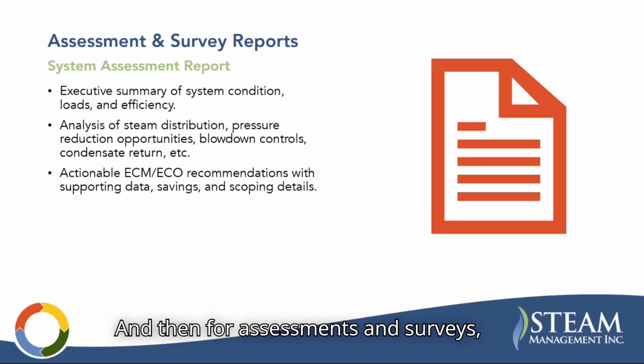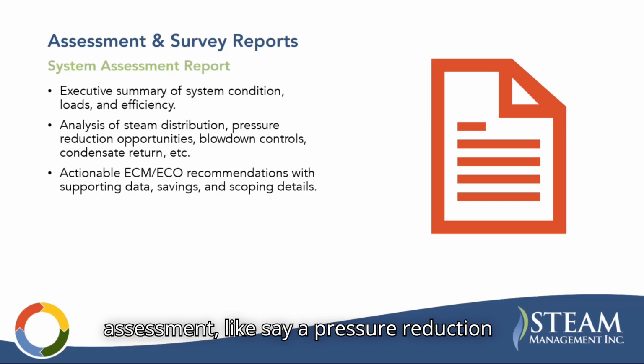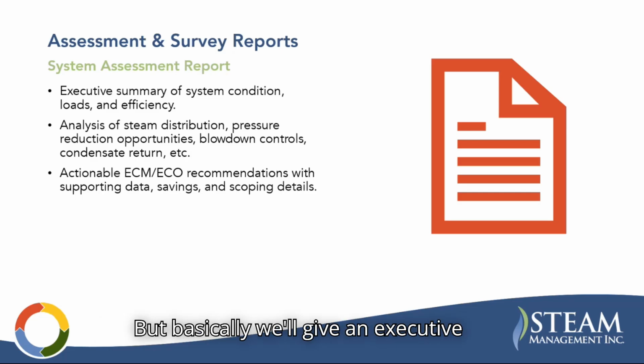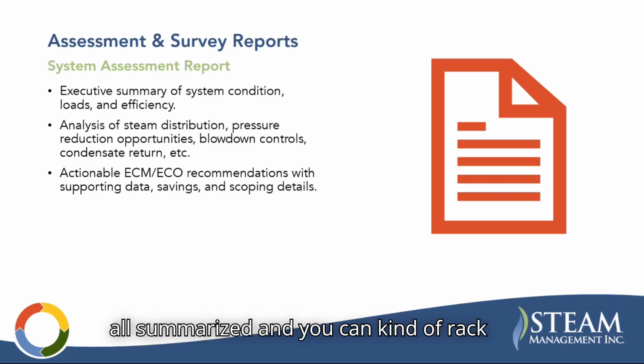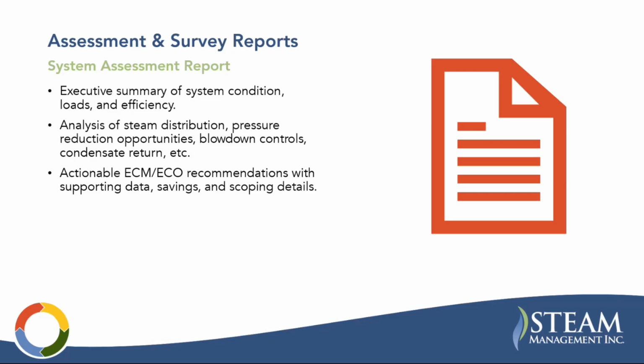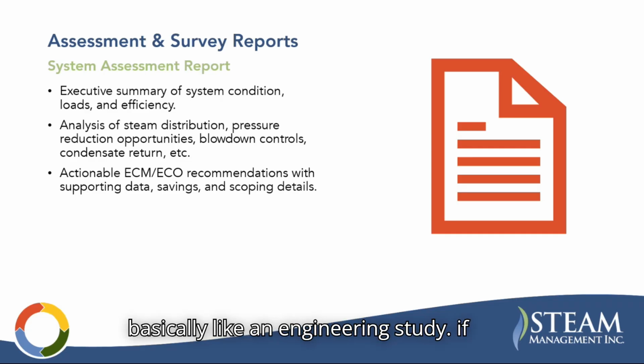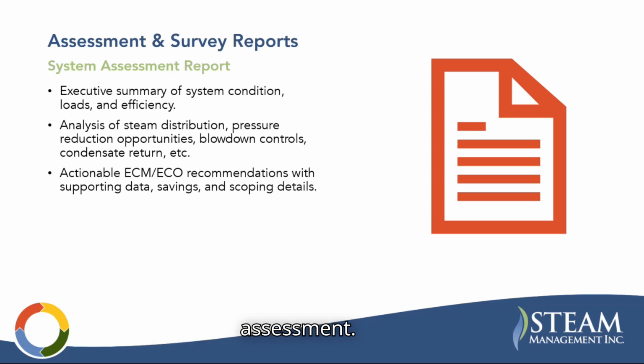And then for assessments and surveys, like an engineering assessment, generally this is a whole system assessment identifying any opportunities. It can be a targeted assessment, like a pressure reduction engineering study or something like that. But basically we'll give an executive summary of the system conditions, loads, and efficiency, analysis of the steam distribution, all opportunities, pressure reduction, blowdown, anything that we see, and have a section for each opportunity with savings, opportunity description, rough order of magnitude costs, and scope description. Those are all summarized, and you can rack and stack opportunities and see what makes sense. So it's basically an engineering study if you're doing a full system assessment.